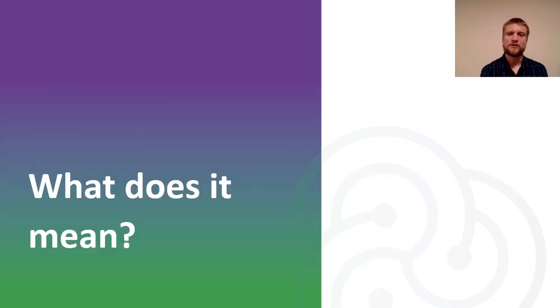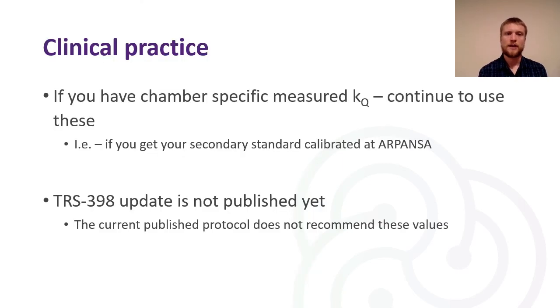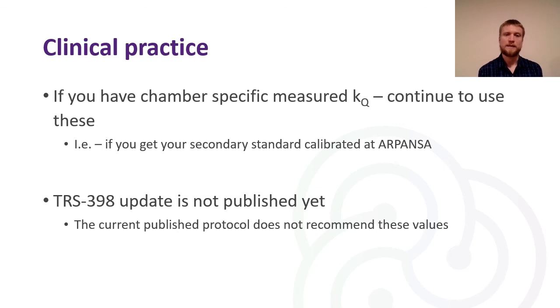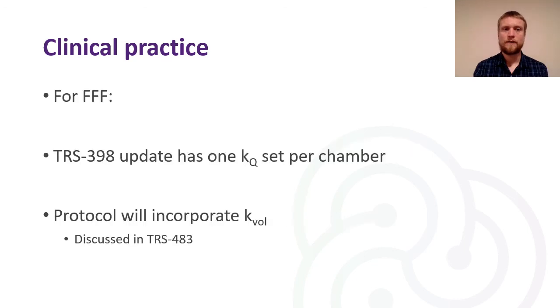If you have chamber-specific measured KQs — the ones we provide when you get your secondary standard calibrated at ARPANSA — we recommend that you continue to use these, as they are chamber-specific and match your chamber rather than a generic one, accounting for any small differences that might exist. The TRS-398 update is not published yet, so the current published protocol does not explicitly recommend these values, but they have been provided so that you may use them if you wish. For flattening filter-free beams, the updated TRS-398 protocol will have one set of KQ values per ionization chamber type, and the protocol will also include the volume averaging correction factor KVol, as described in TRS-483.